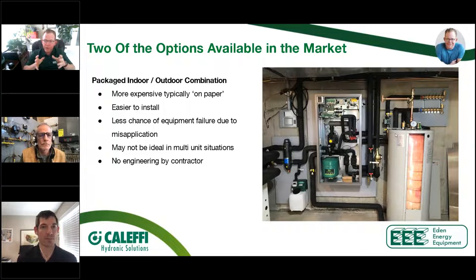One of the nice things about this unit is you have less chance of having equipment failure, because you're not going out there and figuring out how to pipe it. It's literally a pre-packaged unit. You install it, it comes pre-configured, which is pretty nice. It could maybe not be ideal for multi-unit applications, because again, all the controls are packaged into the indoor. This particular unit, I can tell you, this is the unit that Eden Energy has in stock. We stock them in 3 and 5 tons, and we can make this work in a multi-unit application, but there certainly are people who can't. So just, again, be conscious of what the capabilities are.